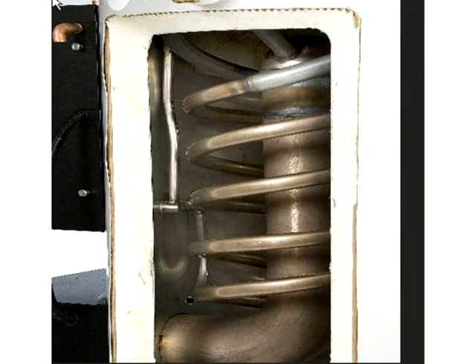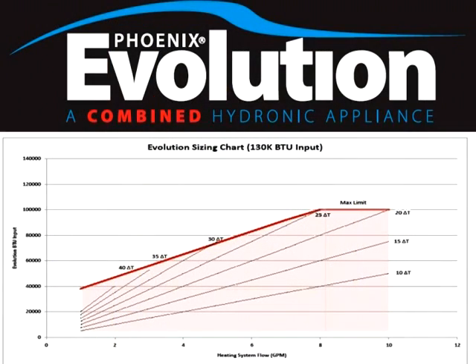So this is a little picture of the stainless steel tube going to the top to extract heat, going to the heat exchanger, and returning from that heat exchanger back down to near the combustion chamber. Now the capacities, this is looking at the 130,000 BTU model. These are available in 130 and 199,000 BTUs, and they're available in 50, 80, and 119 gallons.